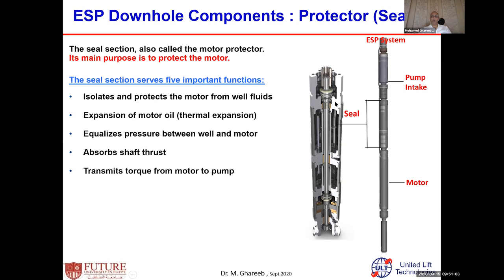What if the motor, from expansion and cooling, starts to lose fluid volume? Then this seal is also filled with fluid which can compensate some of the fluid, and equalize the pressure between them. Also, the shaft of this seal transfers the rotary motion, the torque, from the motor to the intake and then to the pump.